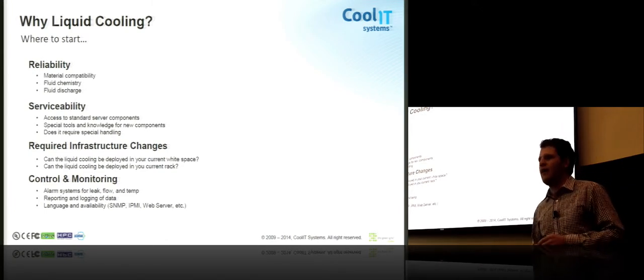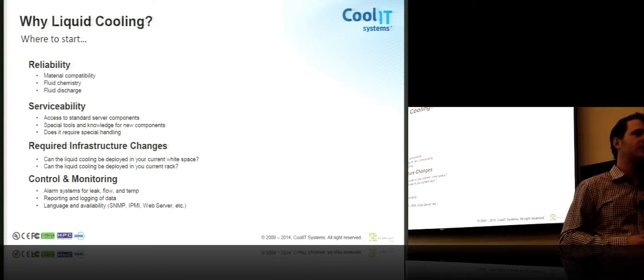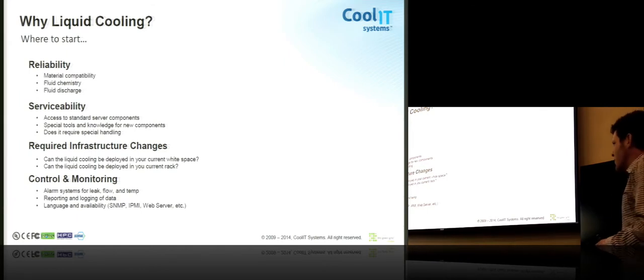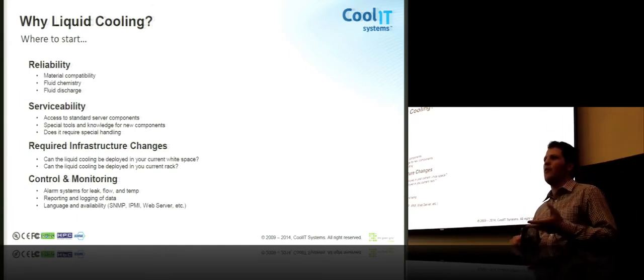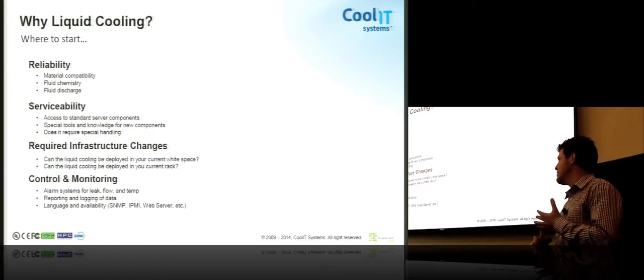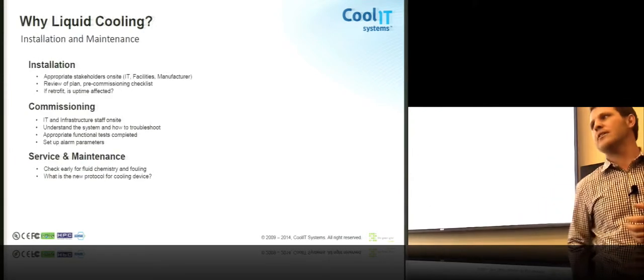Lastly, control and monitoring. I think you all expect that your air cooling systems can be controlled and monitored. There's no reason that your liquid cooling system shouldn't be controlled and monitored. So, what types of alarms do we have for leaks, for flow, for temperature changes, for pressure changes? How do we report those alarms? Is it emailed? Does it work through standard data center languages?